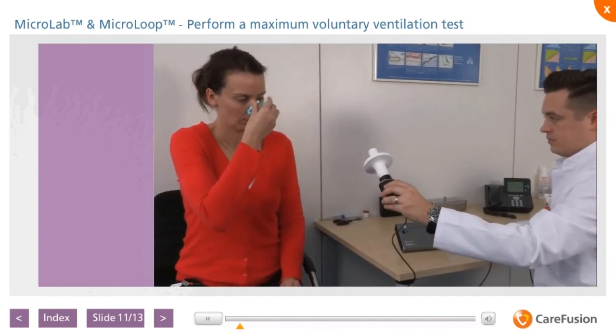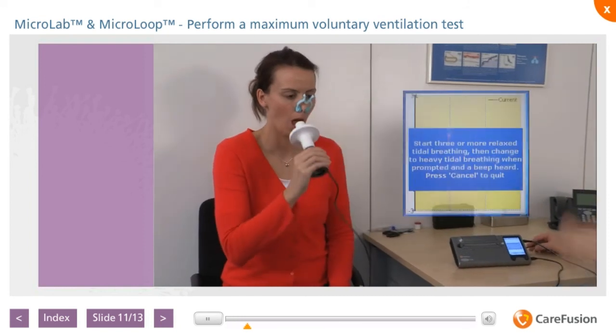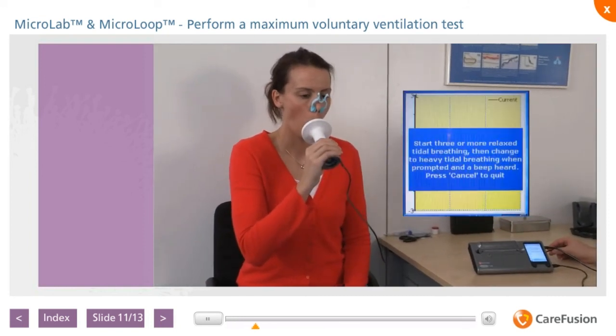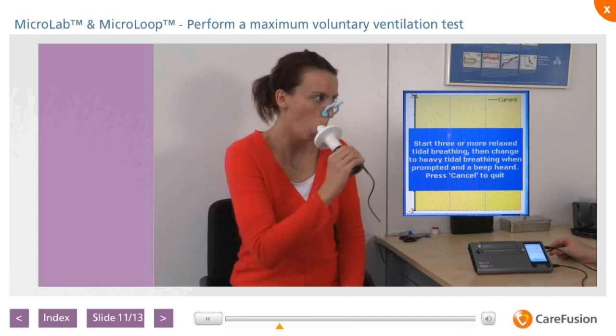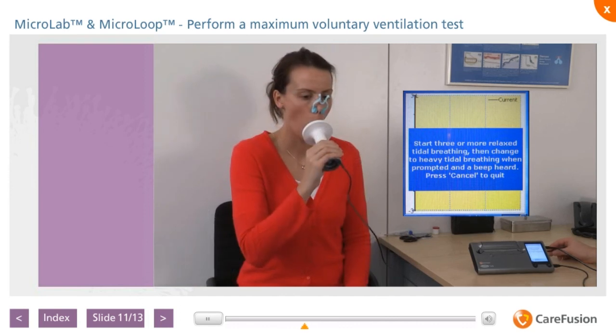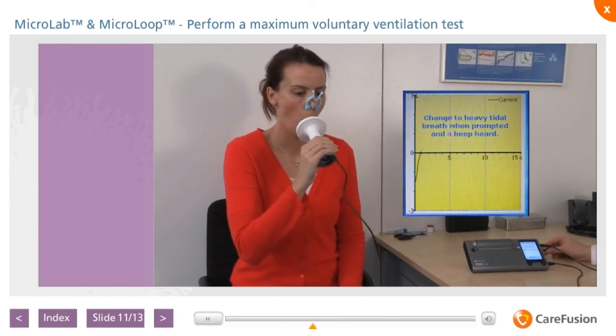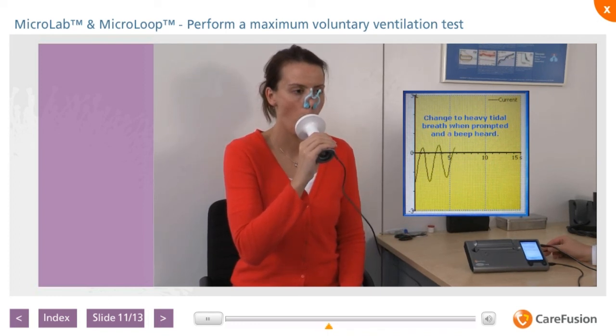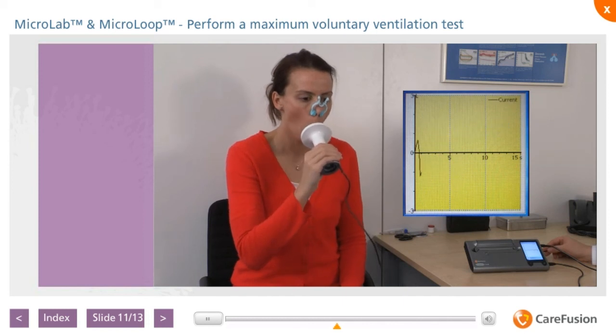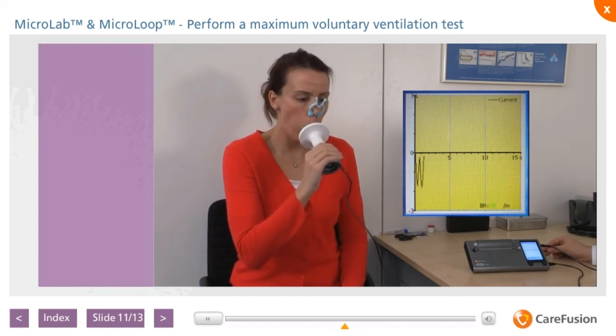To perform a maximum voluntary ventilation test from the main menu, we select the MVV maneuver. With the patient seated, ask him or her to place a nose clip on the nose and the MicroGuard filter or mouthpiece into the mouth. Make sure the teeth are firmly positioned on the housing and the lips form a tight seal. Now ask the patient to tidally breathe out for at least 3 breaths and then start heavy, rapid tidal breathing when prompted on the screen and when they hear a beep.